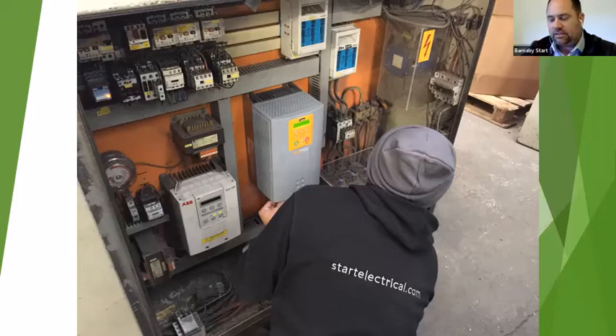The 690, it's a few years ago now, doesn't have safe torque off. So on this one, you can just see the contactor to the right. We utilized the old AC contactor for the DC drive for the isolation.